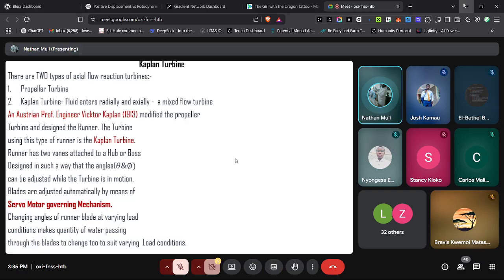If we take 2.0 meters as the diameter of the boss, we can round it off to that. Then that tells us D equals 1.8 times 3, which is 5.5. You can see it is getting us back to that. Otherwise, U is given by pi D N by 60, which is pi by 5.5 by N by 60, and we say 39.6 equals pi D N by 60. When we make N the subject, we're talking of 39.6 times 60 by pi times 5.5, and that translates to 137.5, round it off to 140 revolutions per minute.